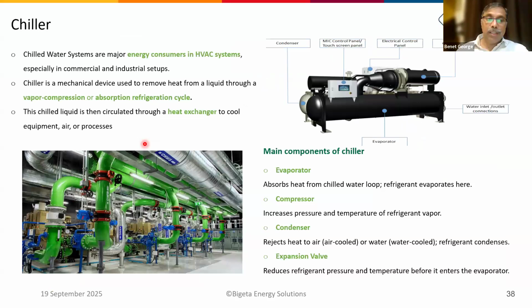Then these are the machines. Many campuses may not have a chiller, but larger campuses may have chillers. It is similar, but the only difference is that in the previous case, the refrigerant transferred heat to the air. But in a chiller, there is a medium in between, water, and the water circulates through the indoor unit. The components, evaporator, compressor, condenser, and expansion valve, remain the same in both cases, but the sizing will be quite high. Typically chillers can range up to 1000 TR for large chillers.